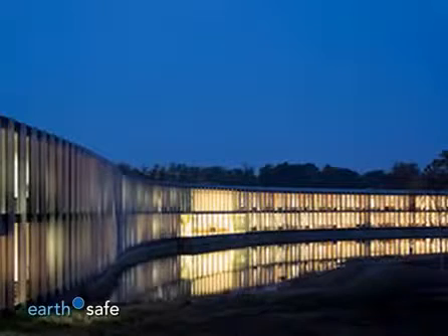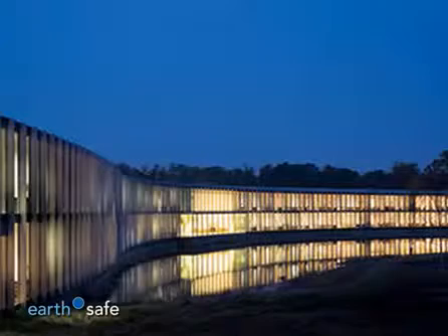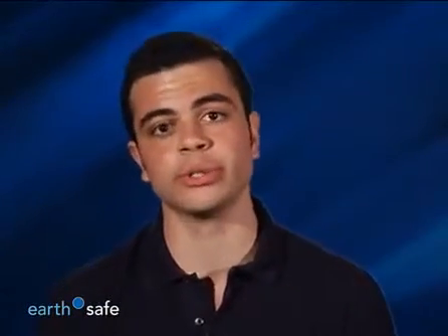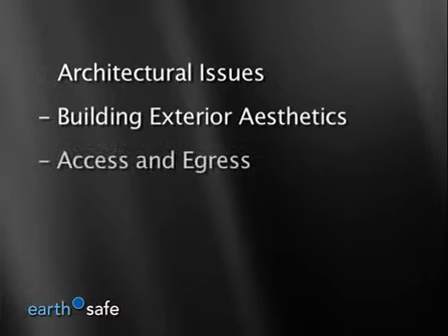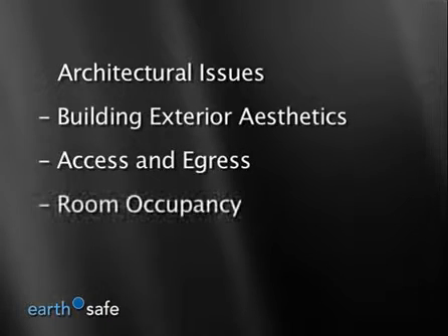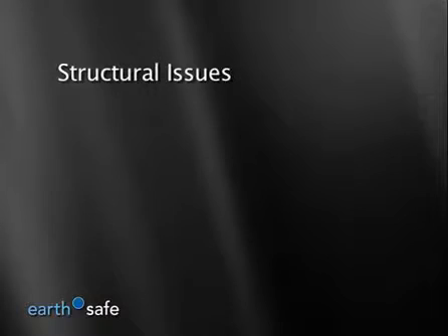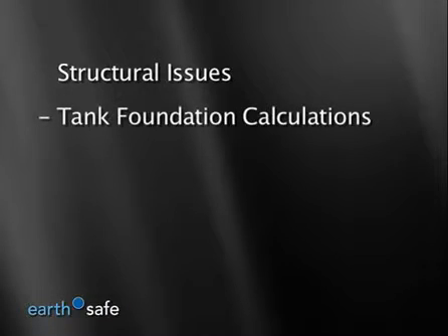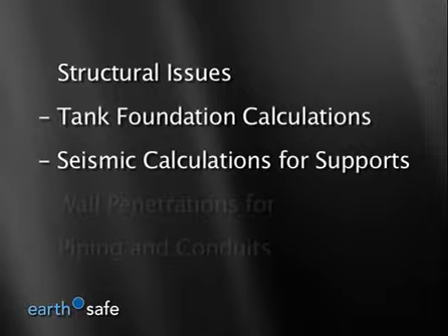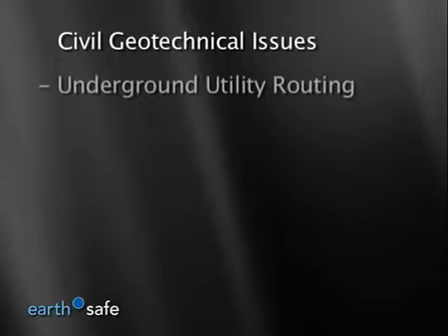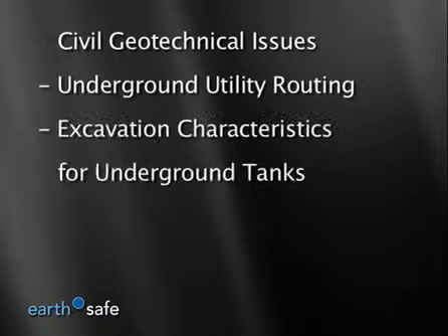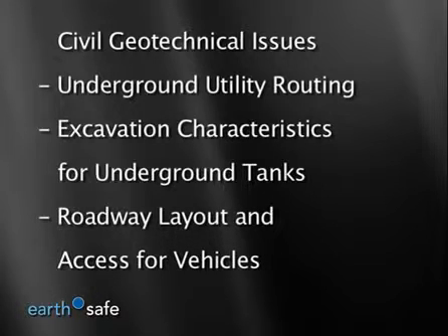Facilities with emergency power systems are critical and complex. A high level of coordination is required amongst the design team. The architectural issues to address are building exterior aesthetics, access and egress, and room occupancy and fire rating. Structural issues include tank foundation calculations, seismic calculations for equipment supports, and wall penetration for piping and conduits. Civil geotechnical issues are underground utility routing and tank area, excavation characteristics for underground tanks, and roadway layout and access for fuel delivery and emergency vehicles.